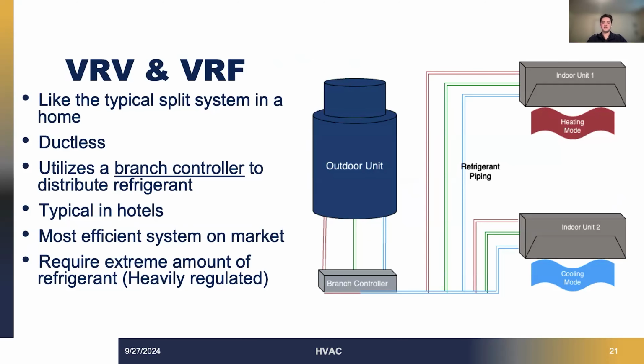One type of HVAC system that is gaining widespread adoption is the VRV, or variable refrigerant volume, and VRF, variable refrigerant flow systems. These two systems utilize similar technologies, but are produced by competing brands. These units are ductless, much like a typical home unit or rooftop unit, and do not rely on water for cooling air. A significant advantage of VRV and VRF systems is their ability to provide varying cooling and heating loads to different sections of a building. This feature makes them particularly well suited for hotels and apartment buildings where multiple tenants have diverse heating and cooling needs.